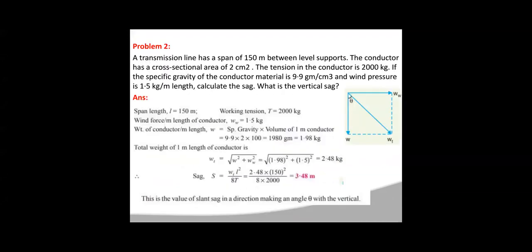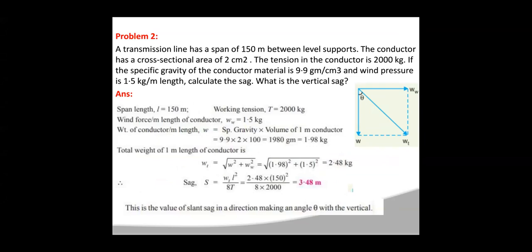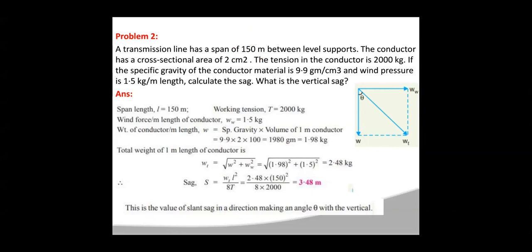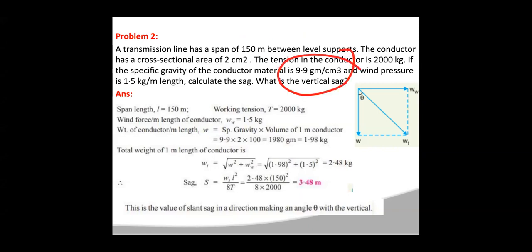Problem 2: A transmission line has a span of 150 meters between level supports. The conductor has a cross-sectional area of 2 cm². Tension in the conductor is 2000 kg. The specific gravity of the conductor is 9.9 g/cm³, and wind pressure is 1.5 kg/m. Calculate the sag and vertical sag. The weight of the conductor per meter W = specific gravity × volume = specific gravity × area × 100 cm = 9.9 × 2 × 100 = 1980 g = 1.98 kg/m.